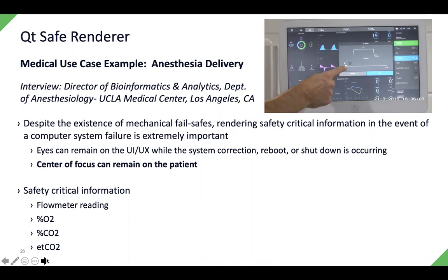The backup system for that anesthesia device, if the digital display fails, goes down, goes blank, is that the anesthesiologist will go and, by hand, control the mechanical valves and look at the needles to make sure there's enough oxygen going to the patient, and at the same time, the patient is still under the anesthetic.